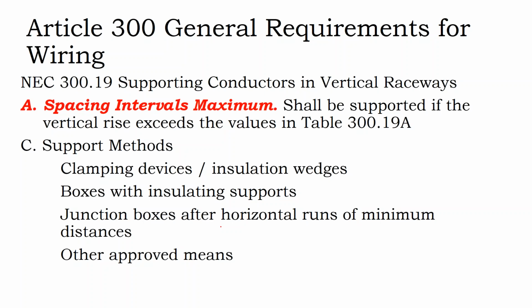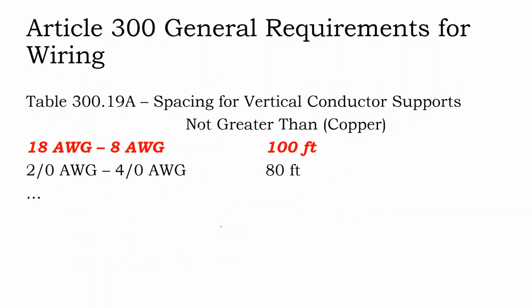Support methods for raceways: not only for vertical runs across a roof, but when you're running wires up and down a building, there are distance requirements, because just the weight of the wire itself can get so heavy that the wire should not be supporting itself. So you want to bolt it to the side of the building and give it a little bit of load relief. But we're talking about spacing that is like 80 and 100 feet. So you only really get into the spacing requirements when you're building 3-story tall buildings, 4-story tall buildings, or wind turbines or something like that.